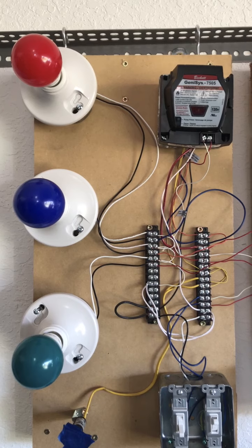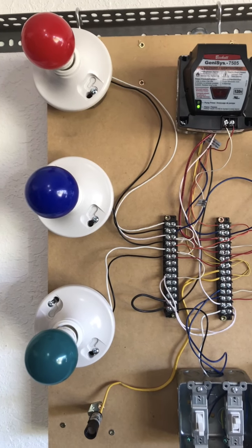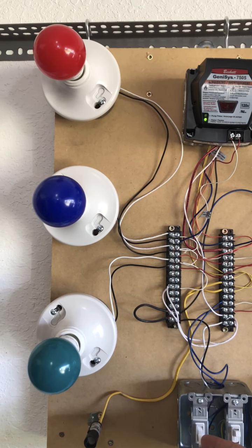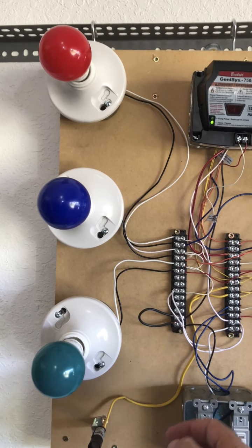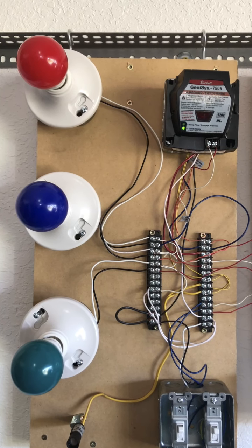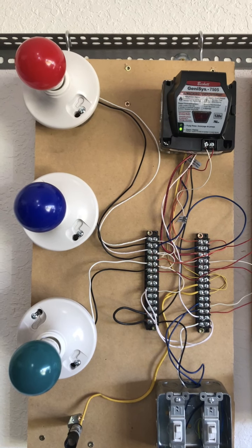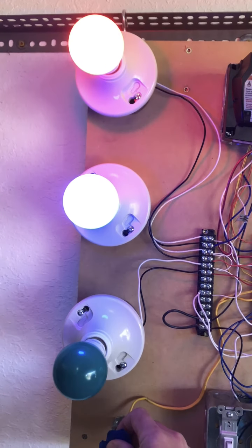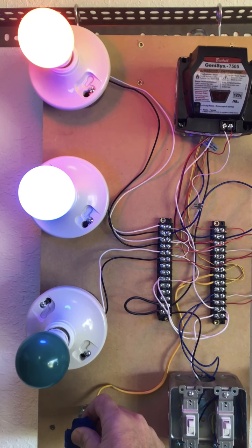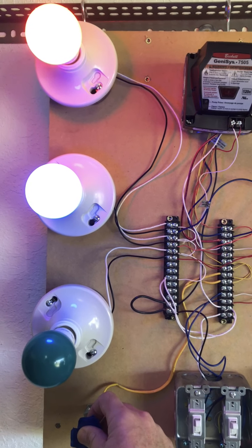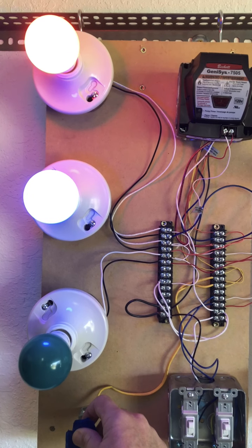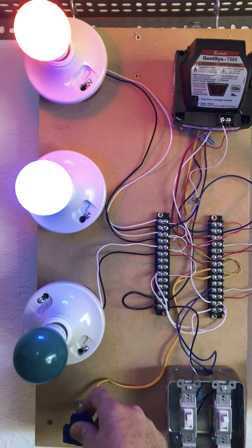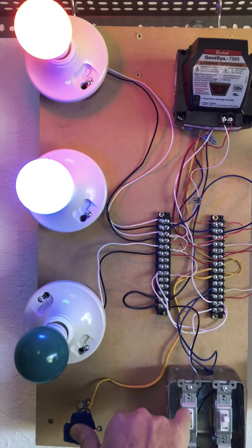Now there's another safety on this as well: it is not going to allow the sequence to run if there's already flame. In other words, if I have light on my CAD cell, it's not going to allow the sequence to start up at all because it already thinks there's light on the CAD cell. The CAD cell has to be in the dark for the whole sequence to start running. That's to make sure that no one has bypassed the CAD cell just by leaving it in the light. Again, the CAD cell tells us if we have flame, if everything's good with the furnace. And this could be a boiler or whatever.